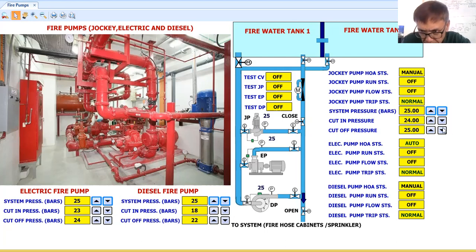Okay, now to be able to show you how it will run, I have done some animation here, by simulating a pressure drop. Then we will see what the cut-in pressure and cut-off pressure of each pump is, okay. Now, as you can see here, in this portion, I have my own BMS graphics, okay. So as I said, the responsible system for control and operation of these fire pumps is the fire alarm system, okay. So this is the firefighting system for the sprinklered building, okay. So it will serve all the sprinklers, then the fire hose cabinets, okay.